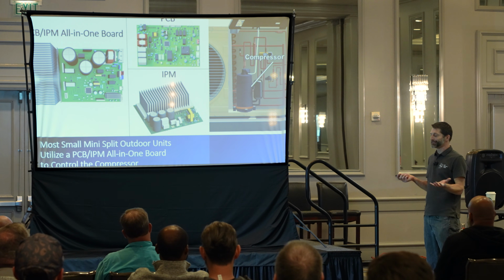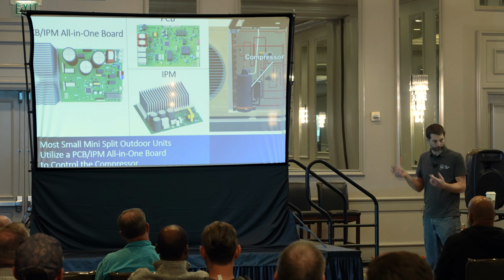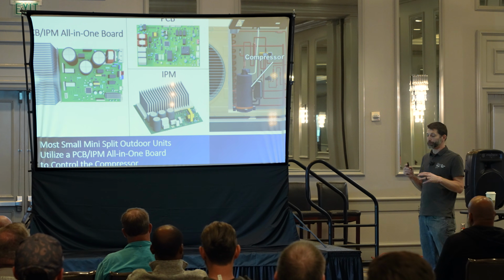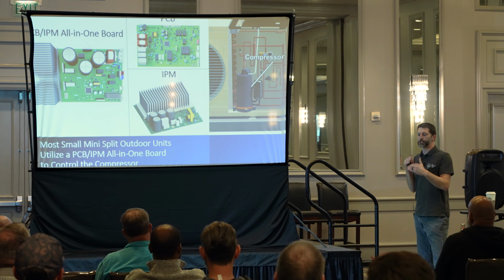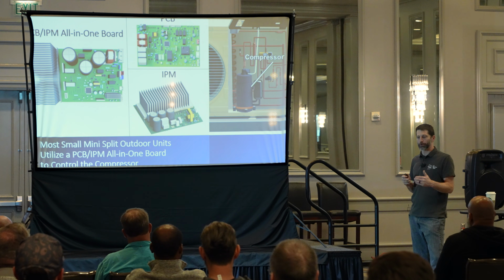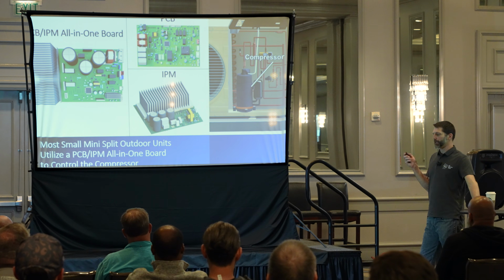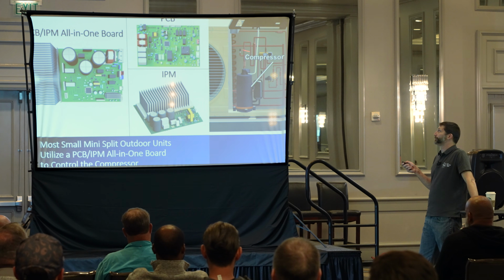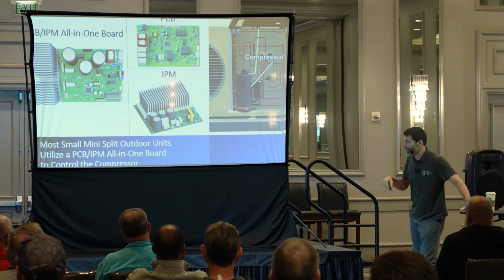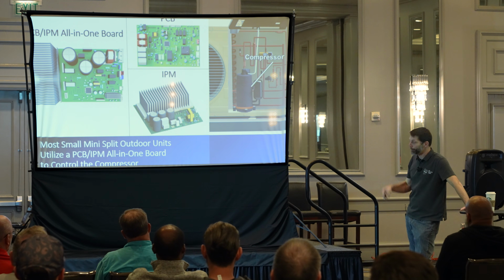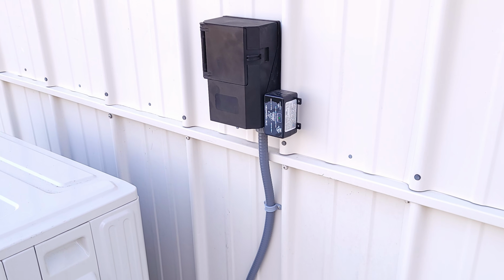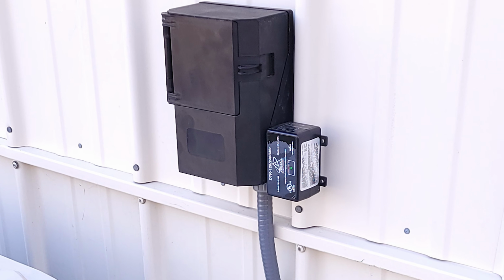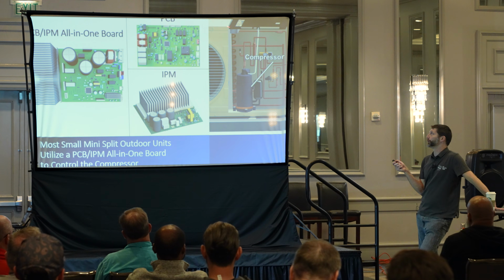And it's not as easy as just throw it away like it used to be with these mini splits. And so they are slowly changing the designs to make them more serviceable. They're trying to improve the designs to decrease the failure rate. And by the way, you better be putting surge protection on these systems. One of the largest causes of failure on a mini split is when the circuit board fails.